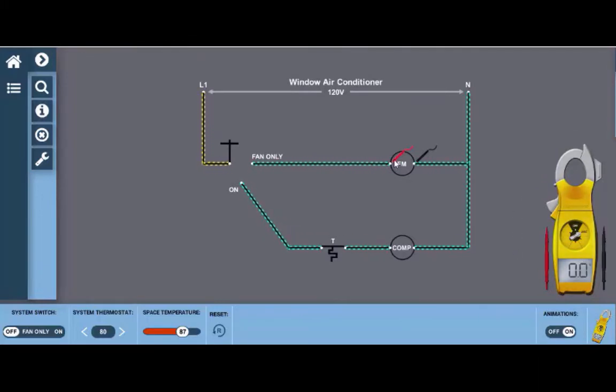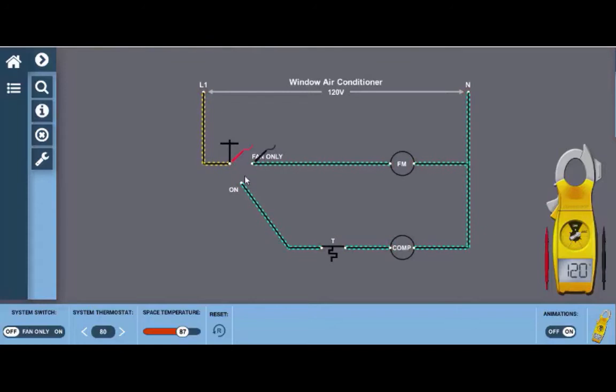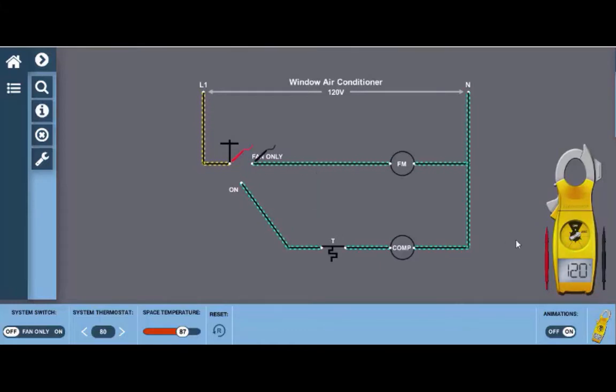This multimeter can also be used for checking the switches. So for example, let's check this fan switch which is currently open. If we put the meter leads across it, we'll have a difference in potential meaning we have 120 volts of potential in but zero out and the way a voltmeter works is it actually reads the difference in potential from one lead to the other.